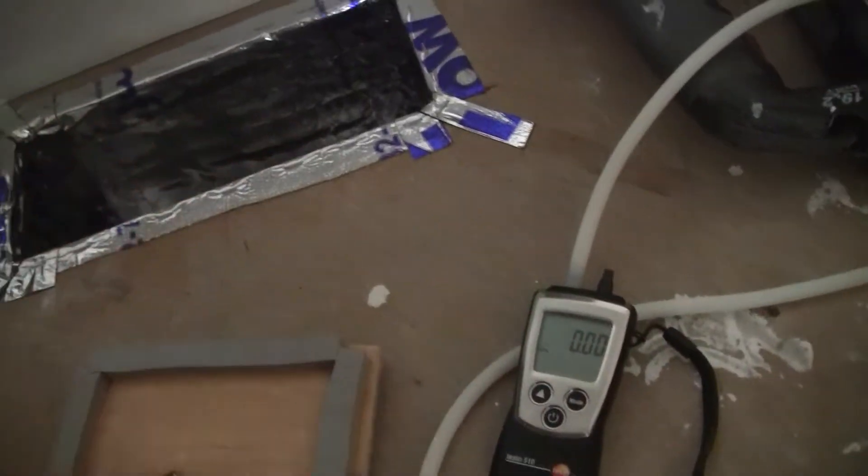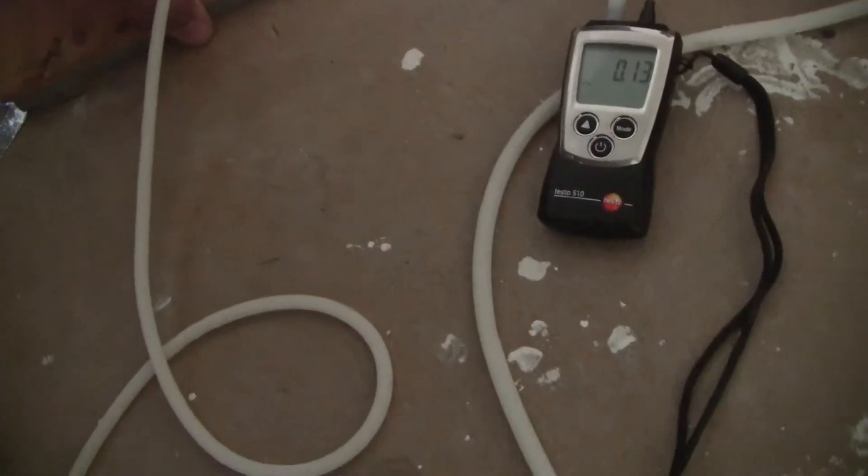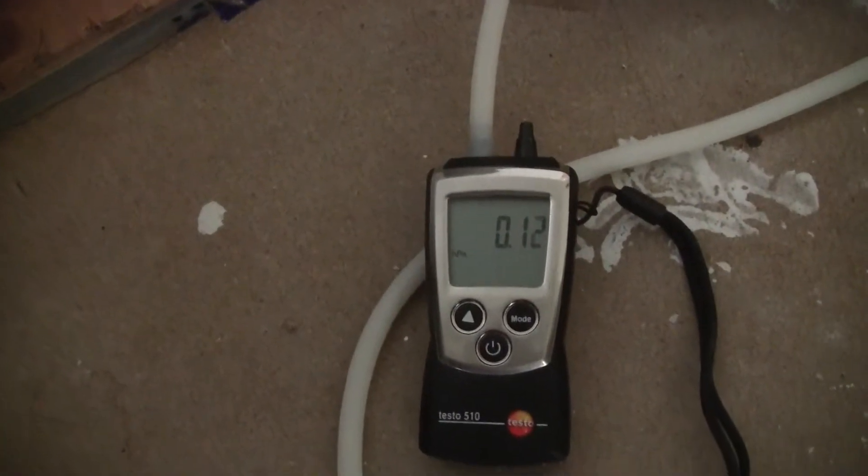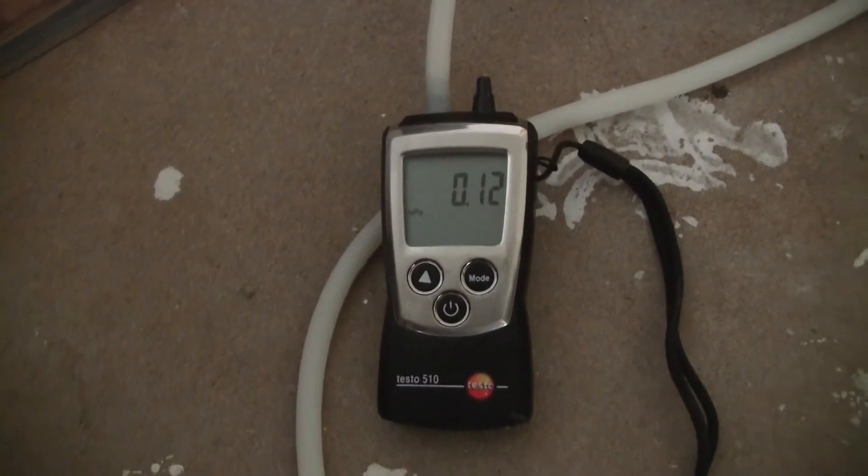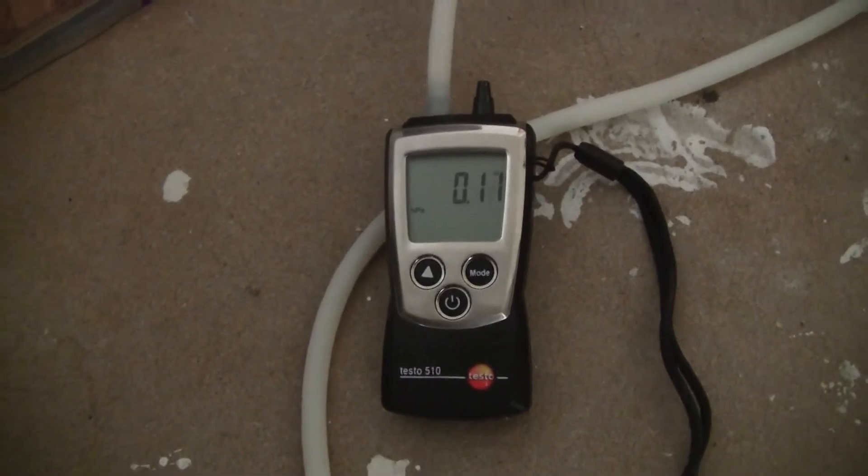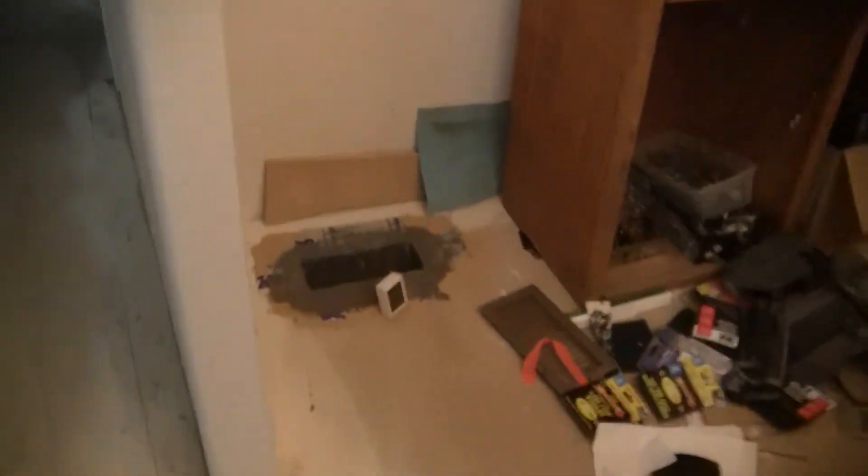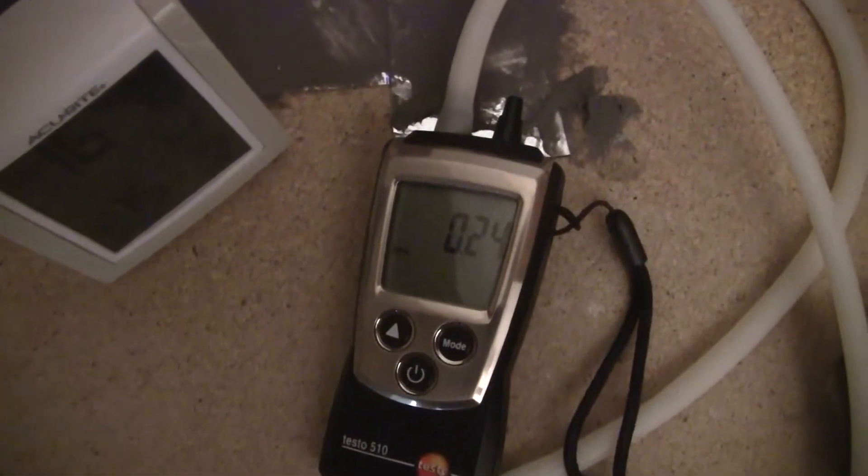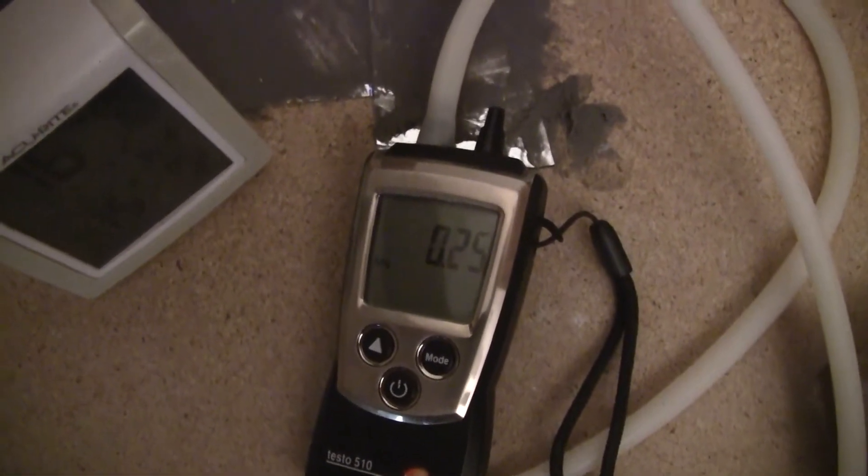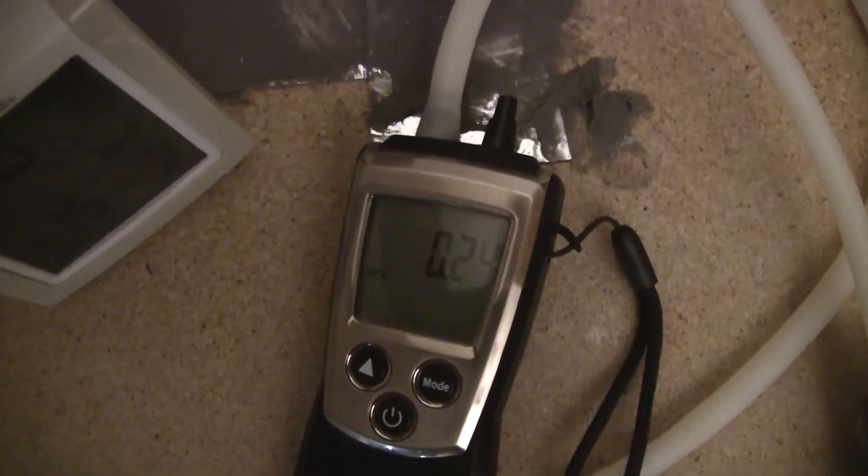0.12, 0.13 pascals. Okay, this is the living room. Now this one's going to be super high because right under it is the vent from the air conditioner. So 23, 24-ish. Okay.